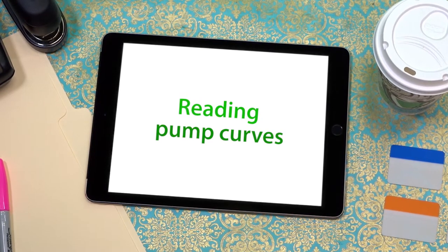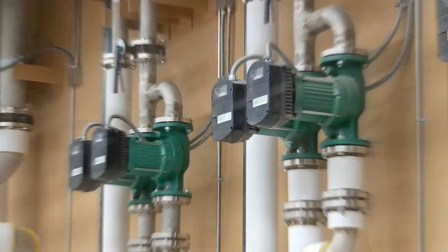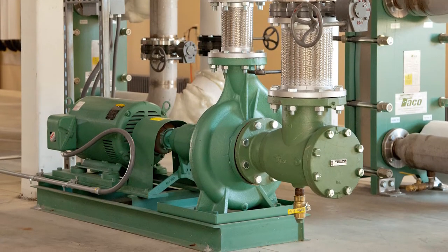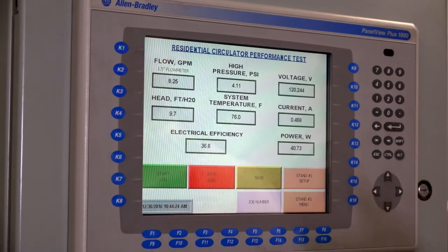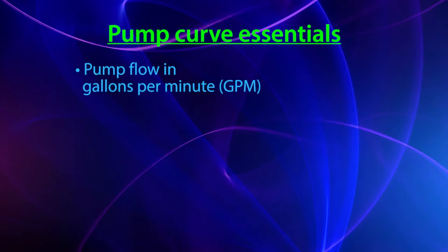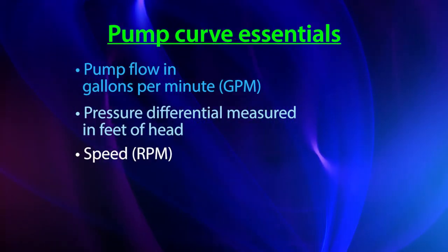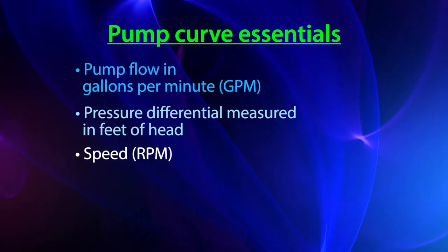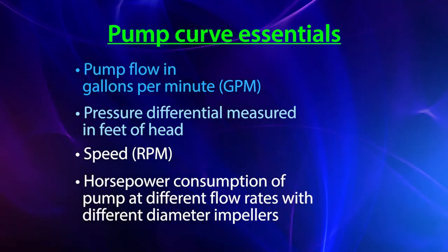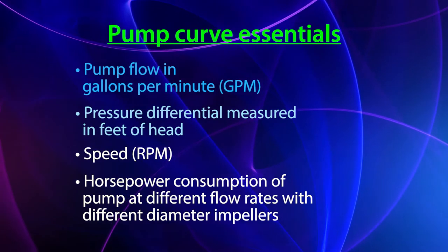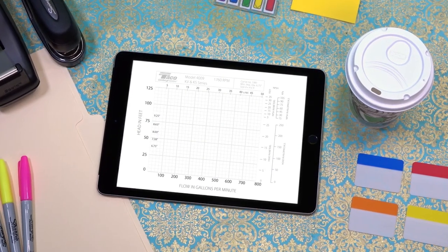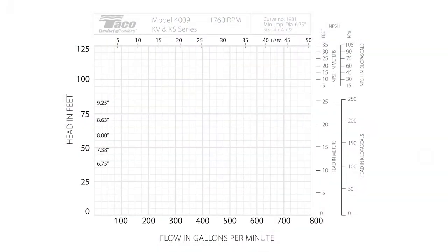To generate a pump curve, we collect physical data from the pump running in the test lab. We mount the pump in a test stand with various instruments and collect the four most important pieces of information: pump flow in gallons per minute, pressure differential measured in feet of head, speed in RPM, and the horsepower consumption of the pump at different flow rates when equipped with impellers of different diameters. We put all this data into a table from which we can plot the pump curve on a chart like this.